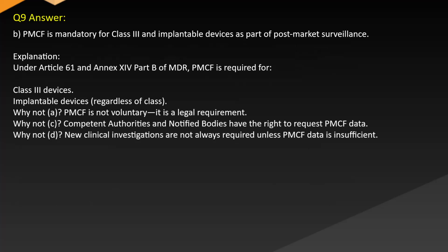Answer. B. PMCF is mandatory for Class III and implantable devices as part of post-market surveillance. Explanation. Under Article 61 and Annex XIV Part B, PMCF is required for Class III devices and implantable devices, regardless of class. Why not A? PMCF is not voluntary. It is a legal requirement. Why not C? Competent authorities and notified bodies have the right to request PMCF data. Why not D? New clinical investigations are not always required unless PMCF data is insufficient.